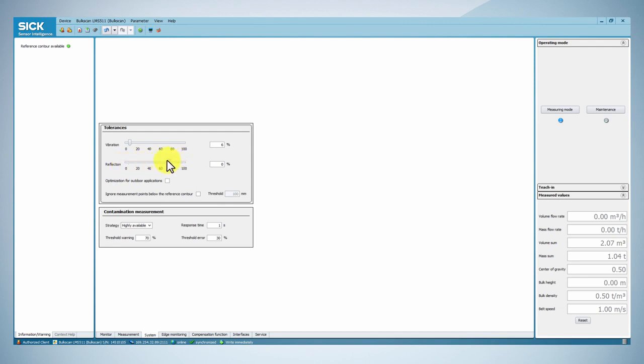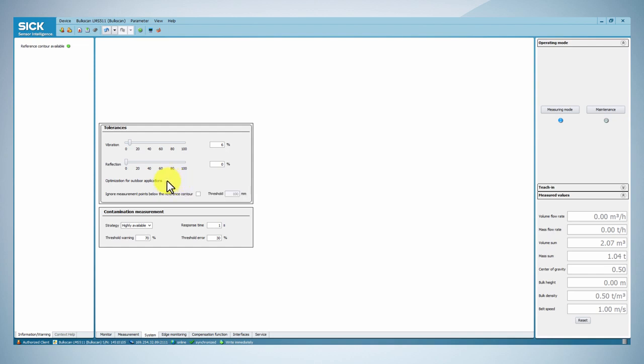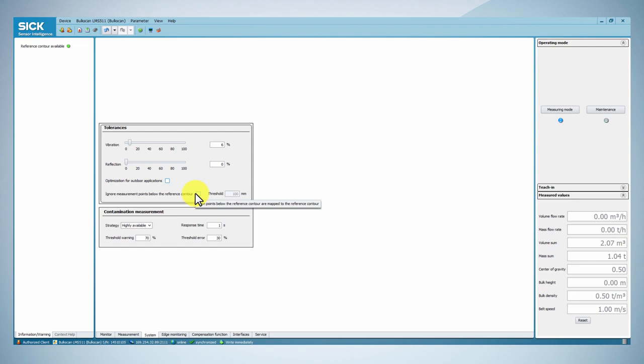Reduce or increase the tolerance against reflection so that the reliability of the system meets your requirements. If you expect external effects such as dust, rain, snow or sunshine reflection on metal surface in your application, you can activate the optimization for outdoor application function in order to avoid invalid measurements.